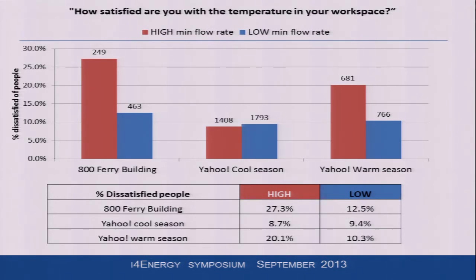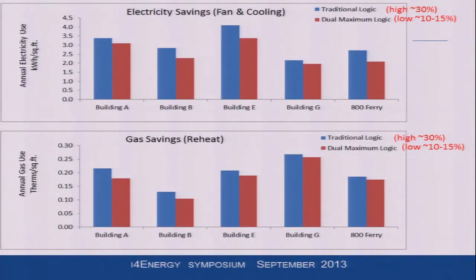So this type of problem happens here, but it happens everywhere. We did a big study in the Yahoo campus, the whole seven-building campus, a big building called the Ferry Building in Martinez. And in this case, by reducing the minima from 30 down to 10%, we not only saved a lot of energy, which you'll see next, but we reduced the complaints in half. So this is the dissatisfaction with the thermal environment. So, wow, this is great. You know, you have a win-win situation possible. Here are the savings that we saw. These are all the Yahoo buildings. The only one that didn't come up with a big saving had a data center in it. But the others are all finding large savings.